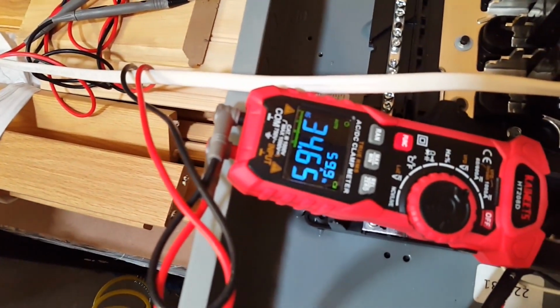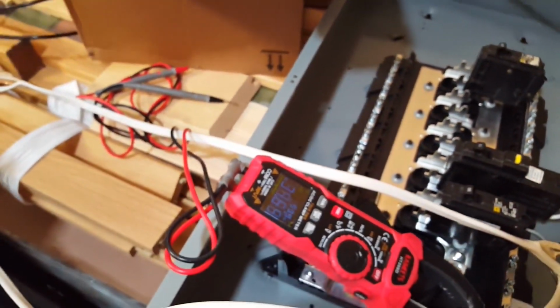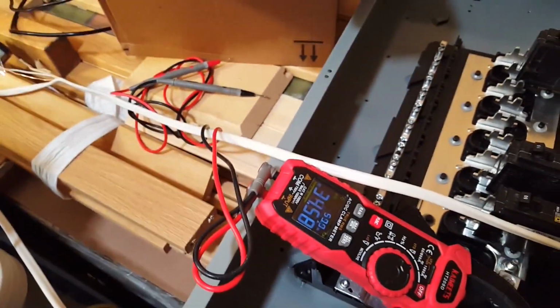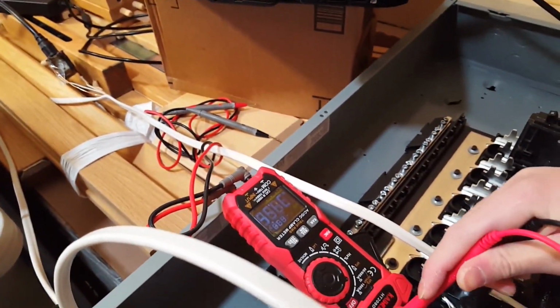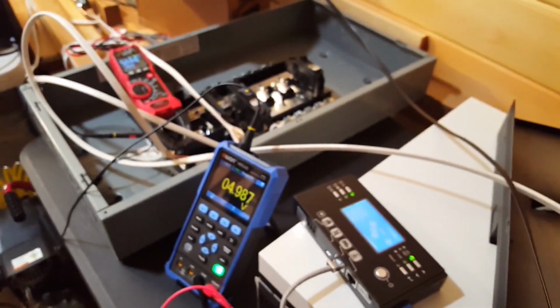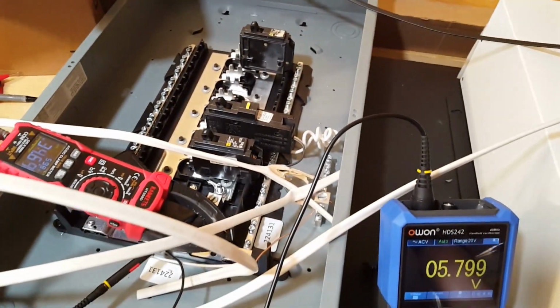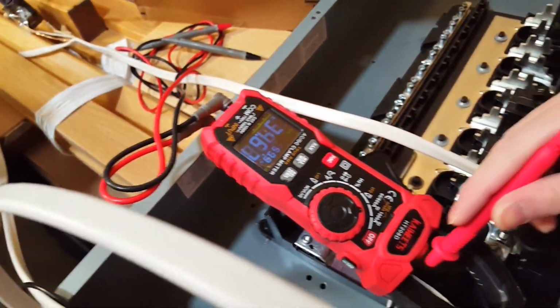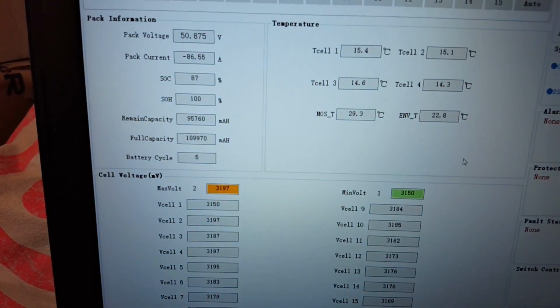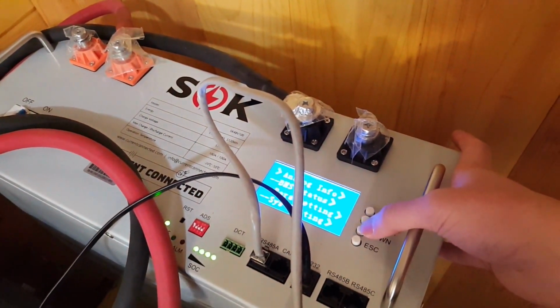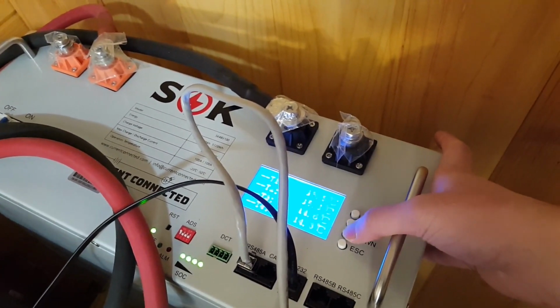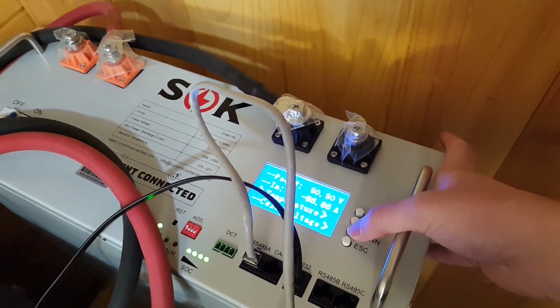So that draws right now 34.62 amps in bypass mode. Let's also check the voltage, 118.3. Let's switch off AC input. Now we're on battery. It's also 34.6 amps. Let's look at voltage, 119, holding strong. Discharging at 86.5 amps. That's the BMS software. Check the battery, 86.7. So basically it's the same.